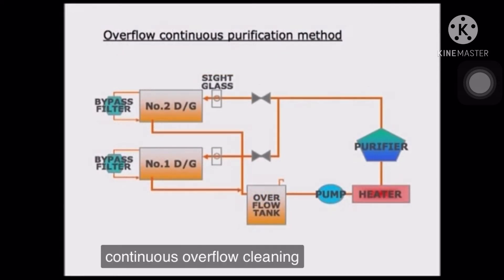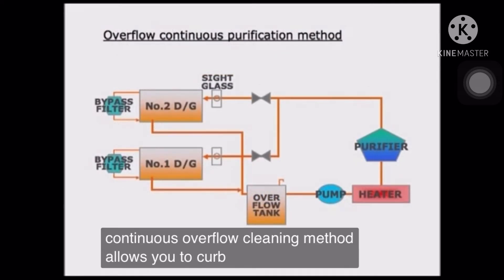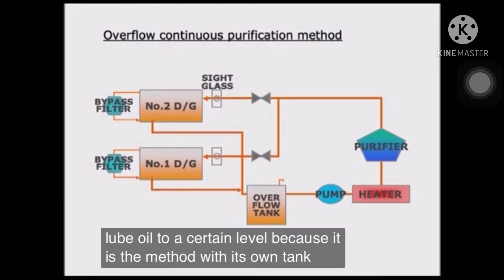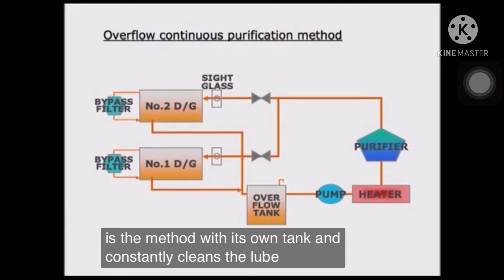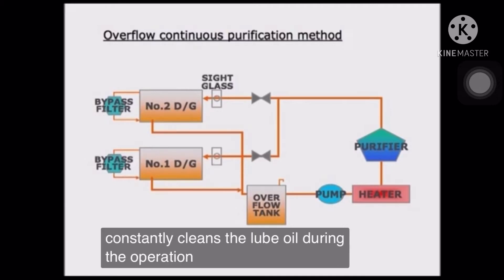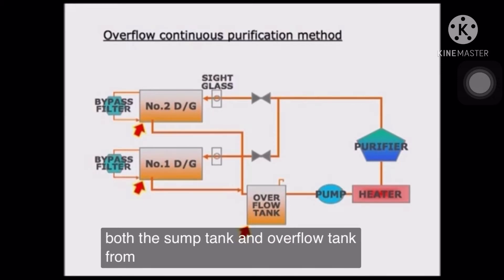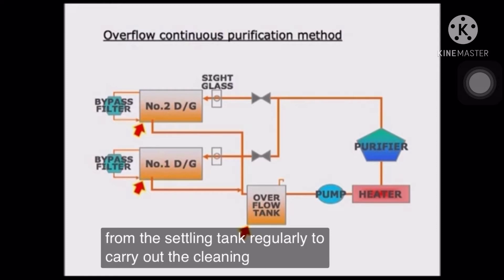The continuous overflow cleaning method allows you to curb the dirt level of the lube oil to a certain level, because it is the method with its own tank and constantly cleans the lube oil during operation. Transfer the lube oil in both the sump tank and overflow tank from the settling tank regularly to carry out the cleaning of the tanks.